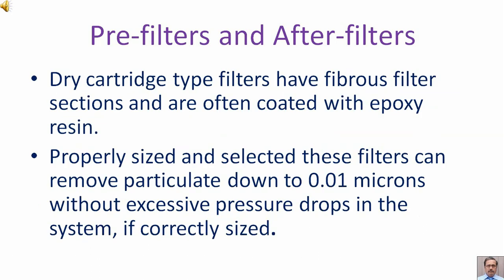Dry cartridge type filters have fibrous filter sections and are often coated with epoxy resin. Properly sized and selected, these filters can remove particulate down to 0.01 microns without excessive pressure drops in the system if correctly sized.